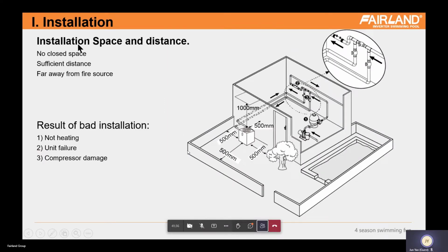And another point is the installation space and distance. We have a standard requirement on the installation space and distance. Normally on the back side, it's at least 0.5 meters. And sometimes it can be a little smaller. As I know, if the air ventilation is really good around the units, then it can be reduced to 0.3. That's fine, if the left side, right side, and the front sides all have very good space, making sure of good air ventilation.